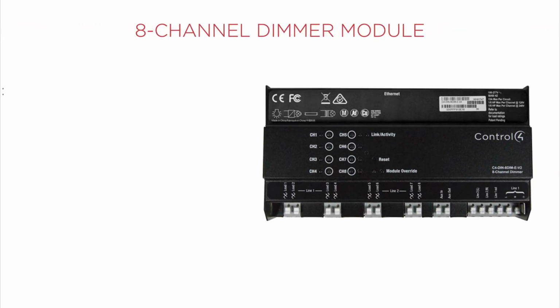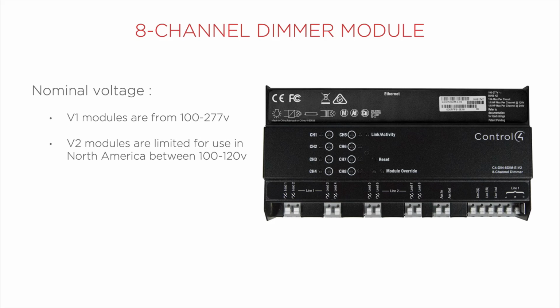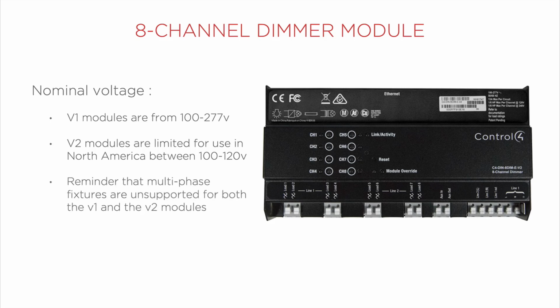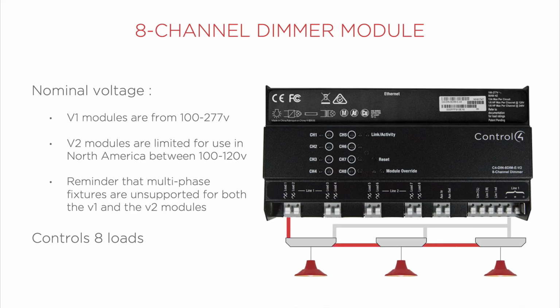The 8-channel dimmer module. The V1 dimmer module is rated for residential and commercial applications from 100 to 277 volts. The V2 adaptive phase and forward phase dimmer modules are rated for residential applications from only 100 to 120 volts. Be aware that neither the V1 nor the V2 modules are rated for use with multi-phase fixtures. The 8-channel dimmer module can control 8 individual loads. A load could be a single fixture or a row of connected fixtures.